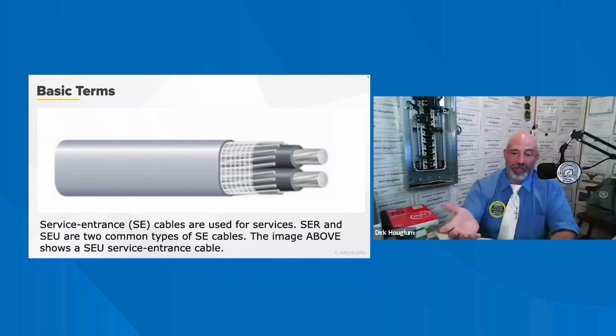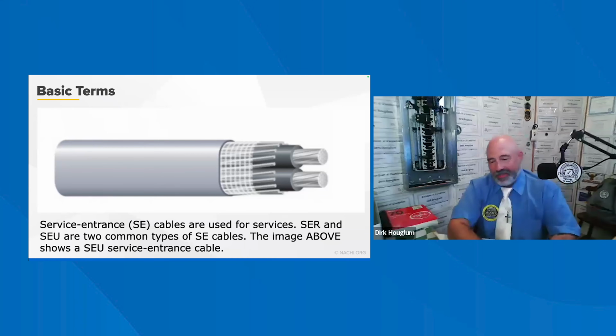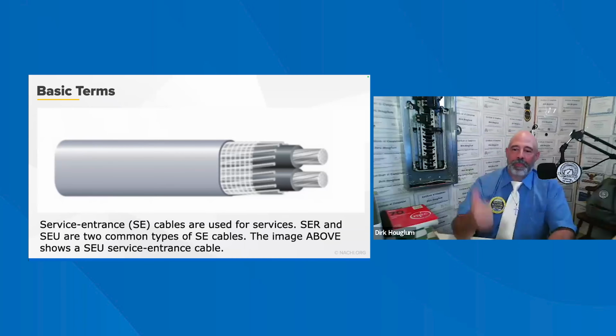The SEU cable has a neutral conductor but does not have a grounding conductor. Since the neutral conductors and grounding conductors are connected at the point of service disconnect, the SEU cables can only be used up to the service disconnect to avoid significant safety concerns. Now the SER, reinforced, that's what it is. Service entrance reinforced.